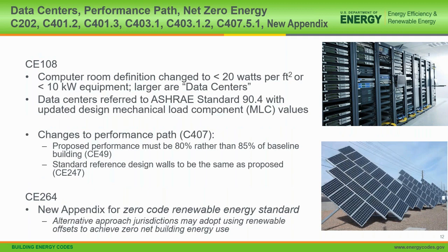All right, moving along, computer equipment, data centers. We've got several items here. So the first one is making a distinction between a computer room and a data center. A computer room is either lower density, less than 20 watts per square foot of equipment, or it's small, less than 10 kW. That would be covered in the IECC, and this aligns with the distinction that's been made in 90.1. Areas with computer equipment that are larger would go to standard 90.4, ASHRAE standard 90.4, which is designed specifically for data centers.